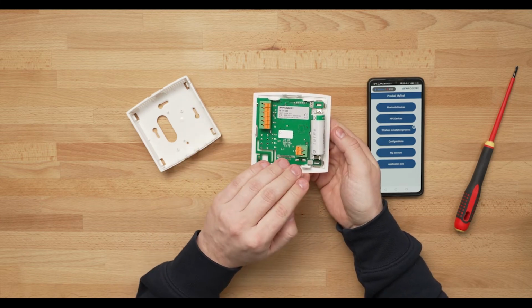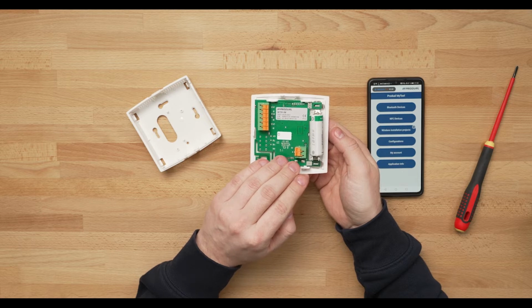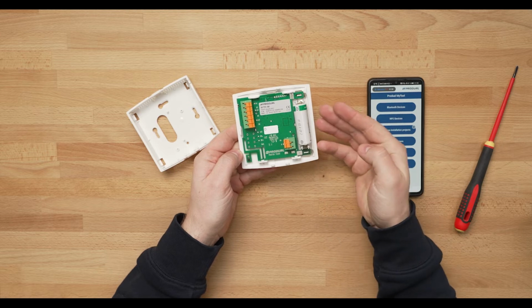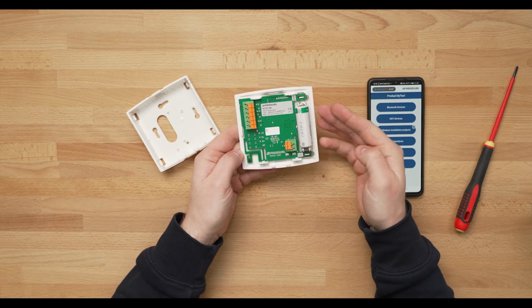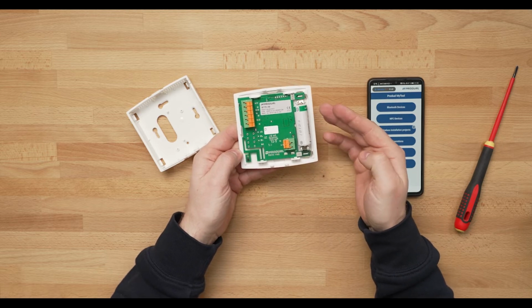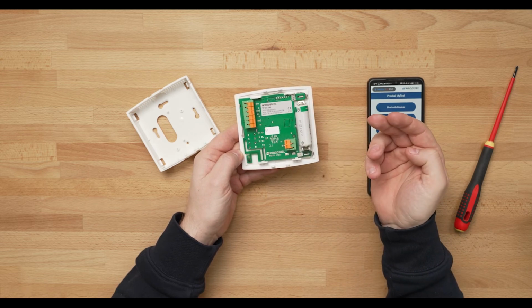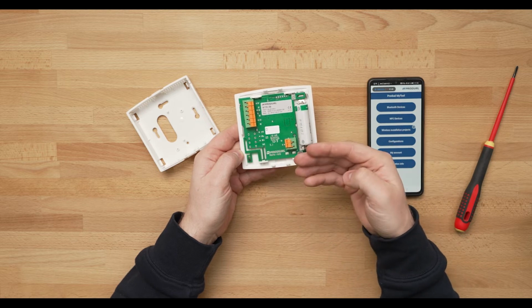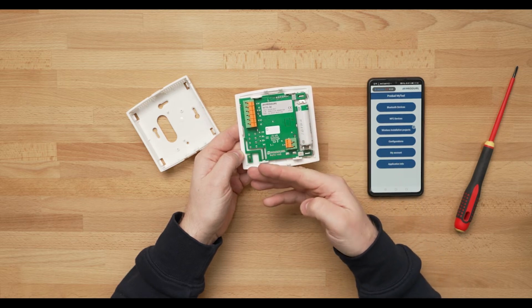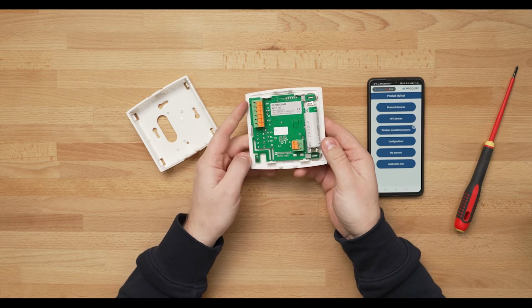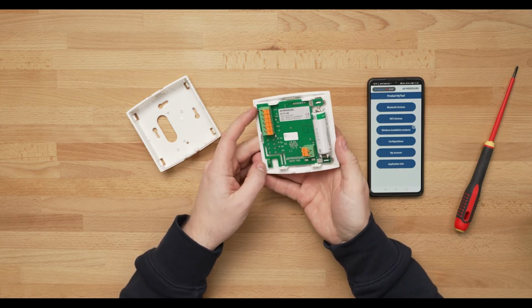Also, we have the possibility to have an external power supply from 10 to 30 volt DC or AC. WTR-IM is also possible to power up with the battery or use this battery as a backup power supply if the main power supply is lost. IM also includes temperature and humidity measurement on the PCB, so this is a very multi-usable device.